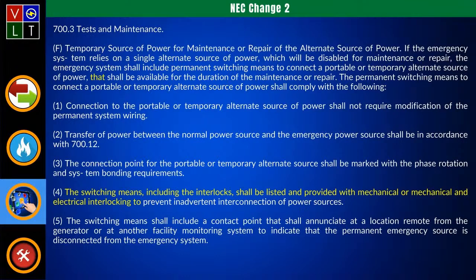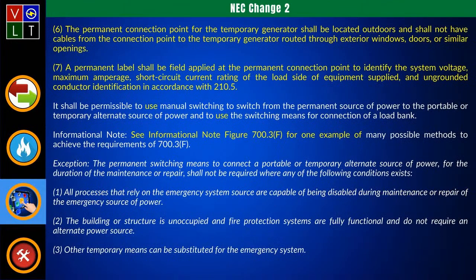Yes, sir. Now, the reason this is put in here is because this is where you have a temporary source of power while you're doing maintenance or repair. And then what they did here is they added (6) and (7). You'll notice they're talking about where you have a permanent connection point for a temporary generator, and that it is located outdoors. It shall not have cables from the connection point to the temporary generator routed through exterior windows, doors, or similar openings. No kidding.